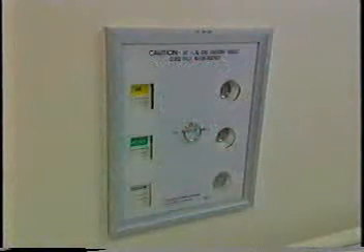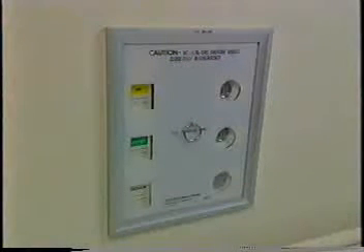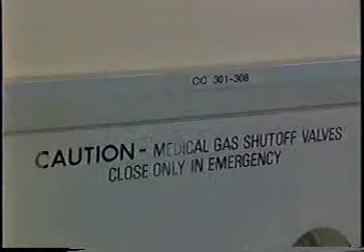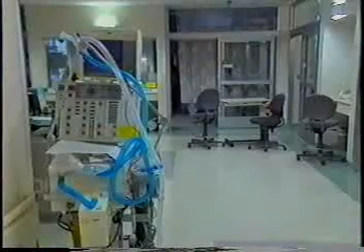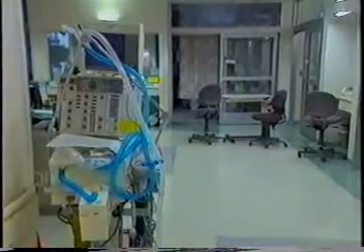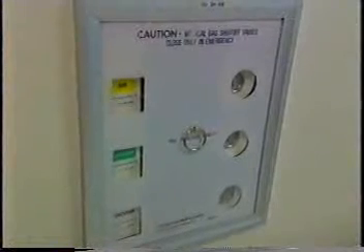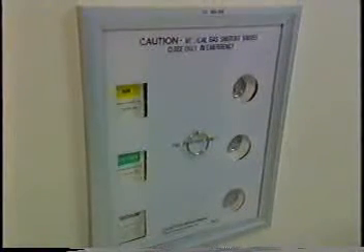Also, in the event of a fire, staff should know the location and who has been trained to properly stop the flow of medical gases in their department. Typically, staff must receive authorization to shut down medical gases, as there should be appropriate prior accommodations made to supply needed gases to patients requiring them during the medical gas shutdown period. It is usually the responsibility of the department manager or supervisor to make this determination. However, all staff in areas where medical gases are utilized or stored should be trained to shut down medical gases in the event of a real fire situation when the flow of such gases presents as an immediate combustion source.